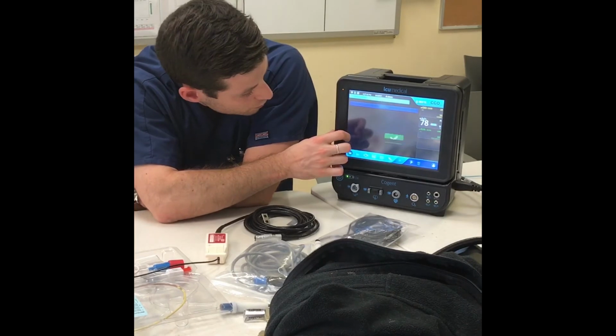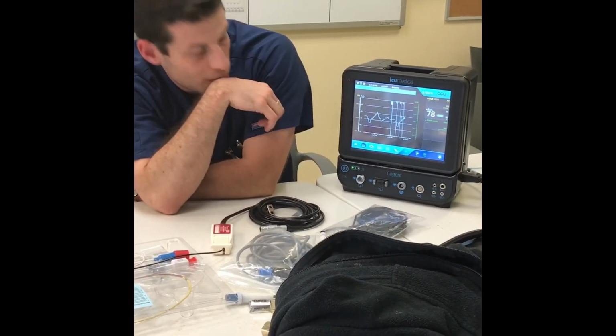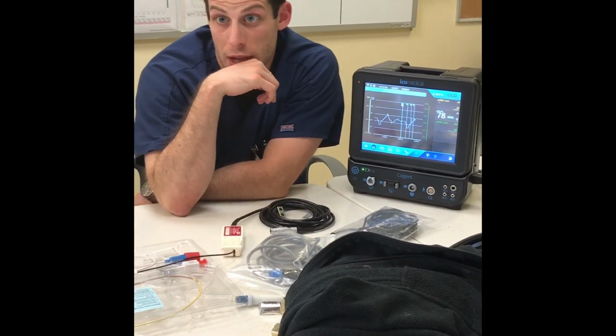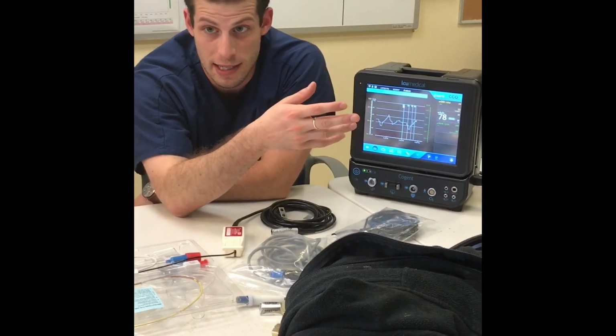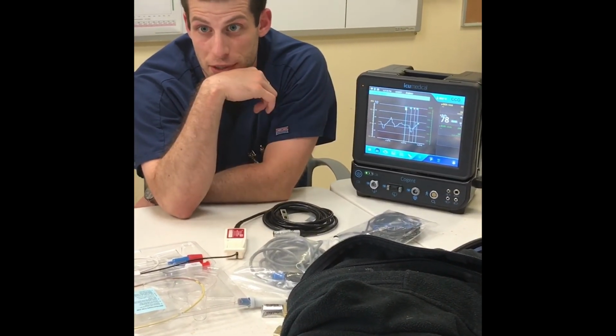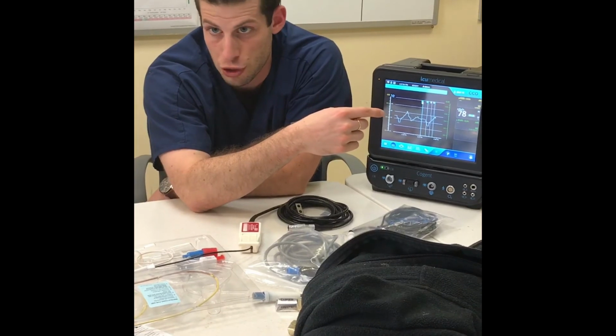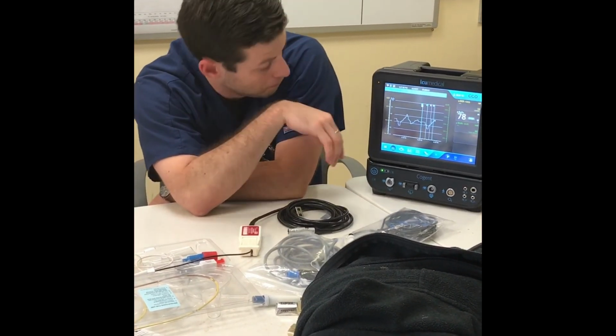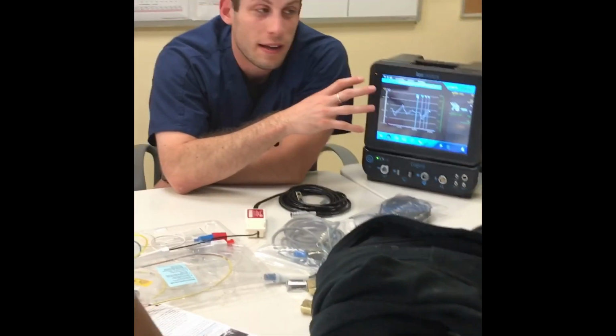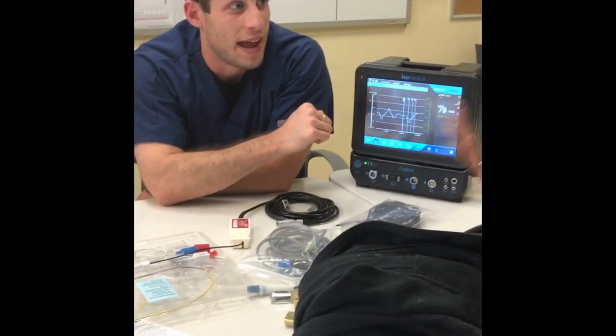So if it's off, because it was 80 and it was 78, then it's okay. But if it came back as 86, then you change the calibration. How do you change the calibration? You just go into enter new cal and it'll come up. Okay. That's what I wanted to know too, because that new number, when you enter it, that's it. Yeah. You don't have to do more.